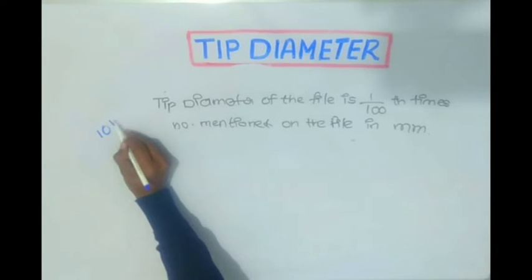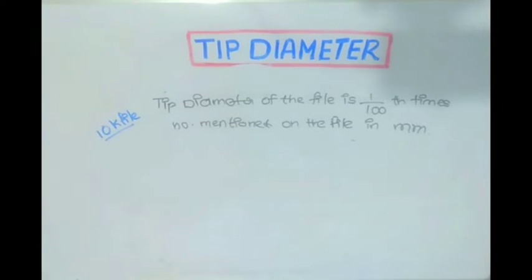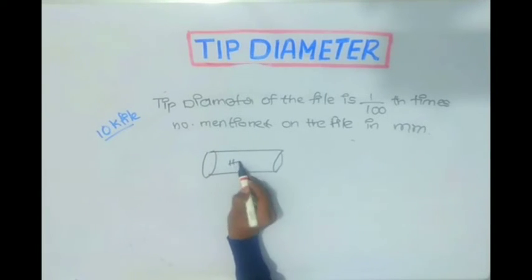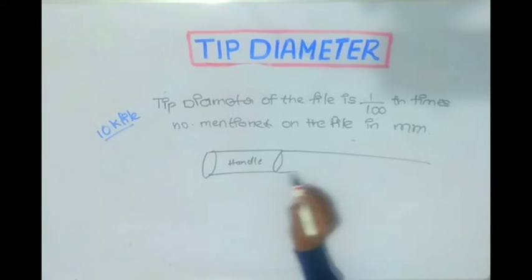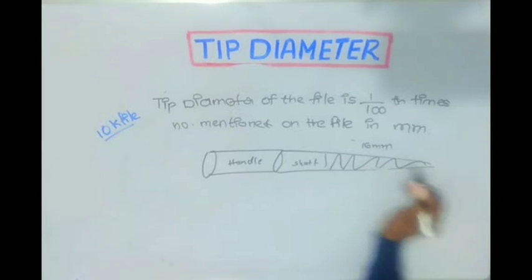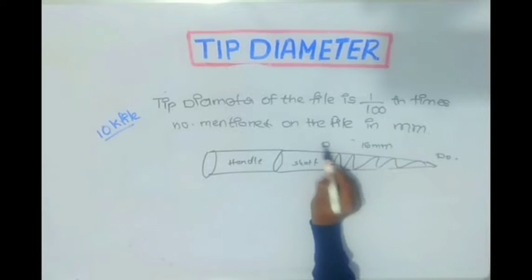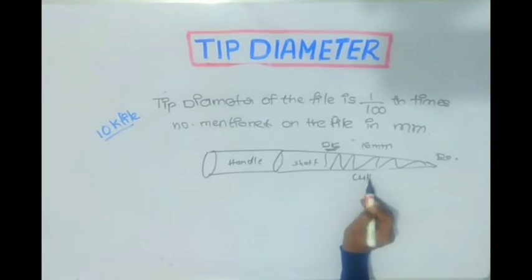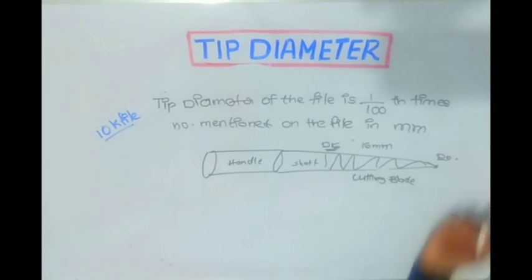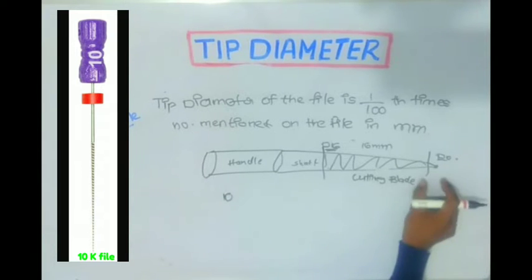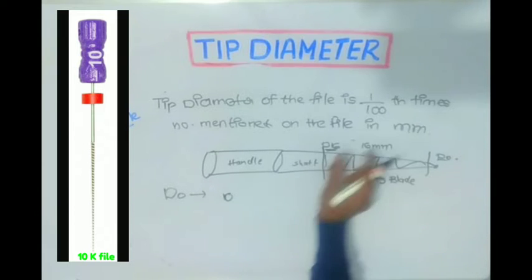When I say a number 10 K-file, what does it mean? Consider this is an endodontic K-file. This is the handle, this is the shaft, and this is the cutting blade — it is 16 millimeters. The tip diameter is denoted as D0, and at 16 millimeters it is represented as D16. The tip diameter, D0, is 1/100th times the number mentioned on the file, in millimeters.